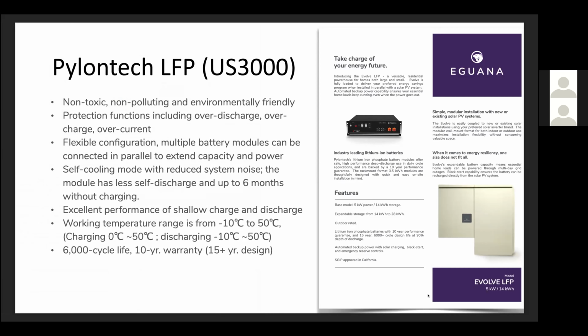So once you've installed a system, say a base system of 14 kWh, and the customer decides that they'd like to add more storage capacity, basically make that bucket bigger, you can come back later and bolt on another DC cabinet and not have to rewire another inverter and run conduit and get new interconnection agreements and all of that stuff. So you can easily add capacity without changing your interconnection topology or your configuration. It does have a self cooling mode with reduced system noise.